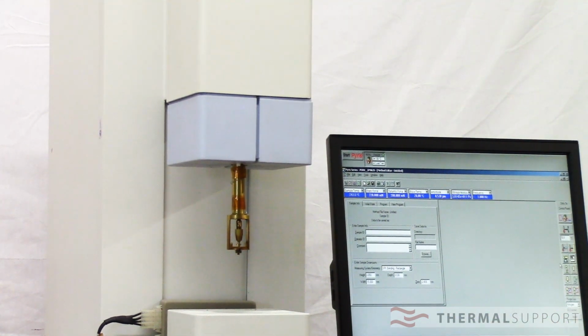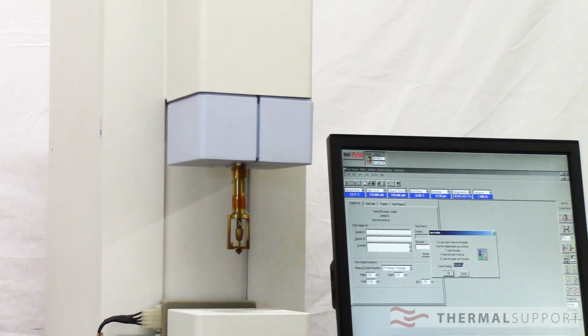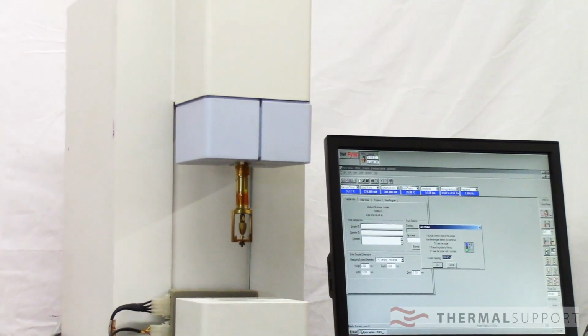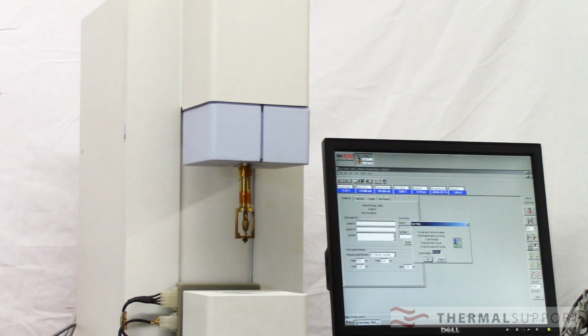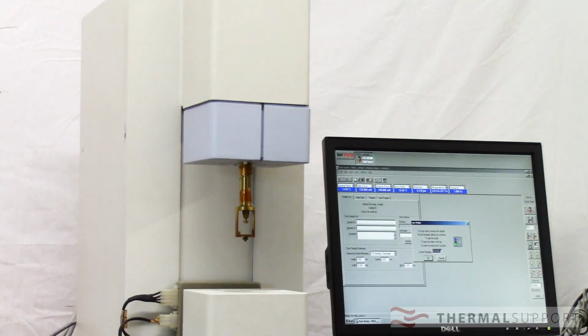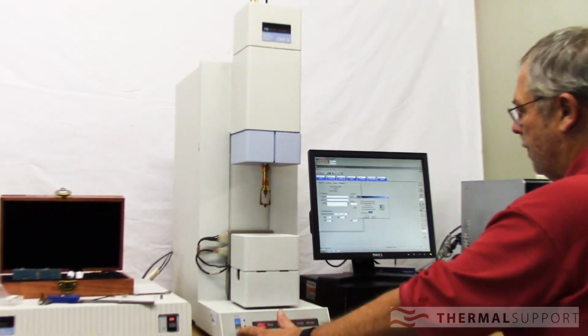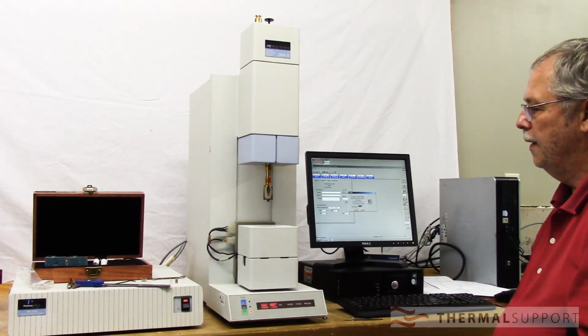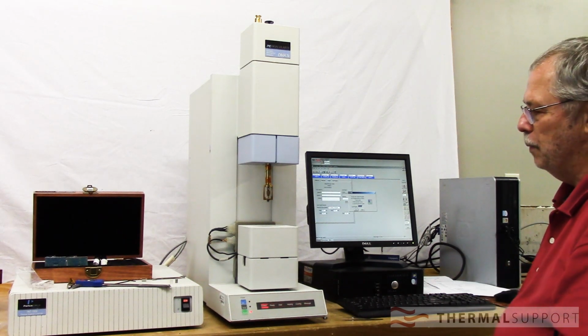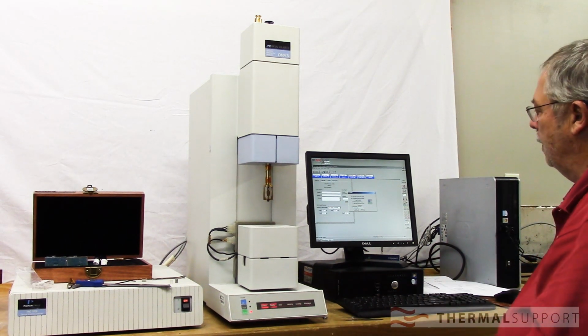One more thing is whenever we start running this, we need to tare it. And what we do when we tare it, we weigh the probe. That's what the taring is. We're weighing the probe. But we've got a platform on there. We need to offset the weight of that platform. So we're going to go up all the way. We're going to come back down. Anytime people are nervous about their instrument, they seem to go up halfway.